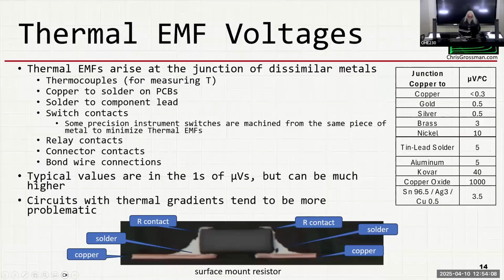Thermal EMF voltages - this is what screws you up when you try to measure small voltages. Thermal EMFs arise at the junction of dissimilar metals. It's the way thermocouples work for measuring temperature - two metals. Where would you see this? Copper to solder on PCBs, solder to component leads, switch contacts, relay contacts. So in precision instruments where you're trying to measure tiny voltages, if they have switch contacts, they'll actually machine the contacts out of the same piece of metal so the alloy is the same.